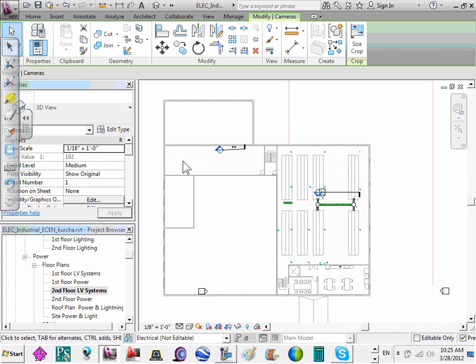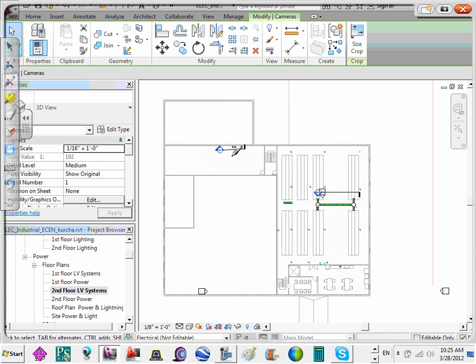So how many do we have? There are 3 air handling units in this area. 3 air handling units. Let me draw them this way. Just here's one here, and one here, and one here. NFPA 72 is where you're going to find your typical symbols. If you're looking at a duct smoke detector, you're going to have it on the return side.